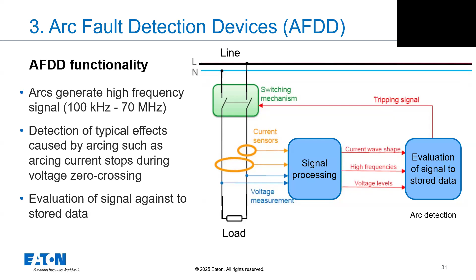Okay, next very important information in the standard for AFDD, and here we have an overview with a picture and explanation. It's the so-called directional sensitivity, or in the standard it is named the crosstalk test. What does it mean? If we have an installation in a final circuit, like we can see in the picture in the right down corner, there is an arc generator which creates, let's say, a serial arc, and this frequency of signal is detected by the AFDD, and this AFDD must switch off.